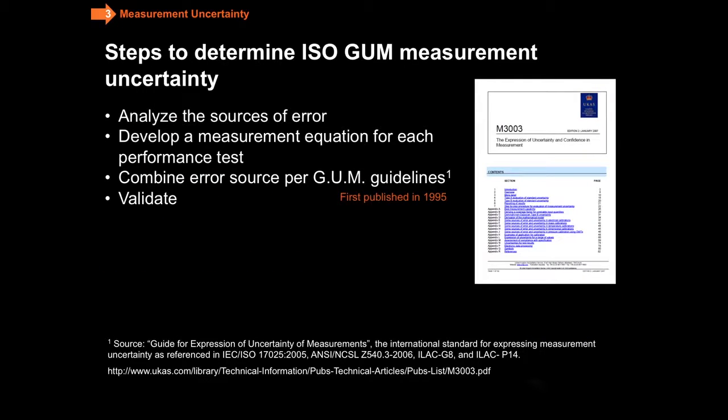How do you accomplish and make an error budget using the guide for expression of uncertainty measurement? So here's the general outline. As you analyze the sources of error, you come up with a measurement equation for each of the performance tests, and then you model the errors and you combine them per the outlines of the GUM, and then finally, as always, you validate.